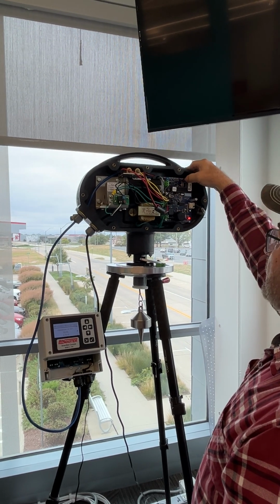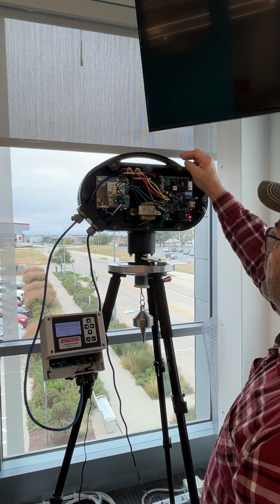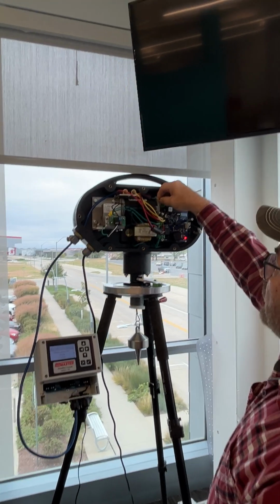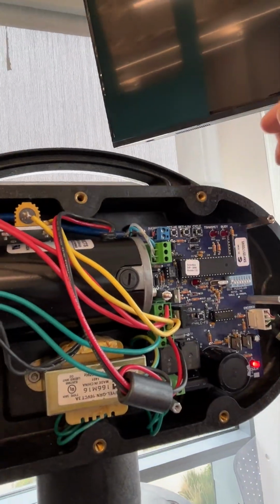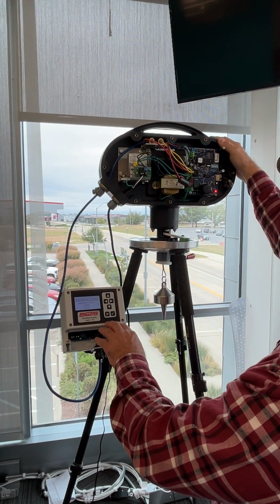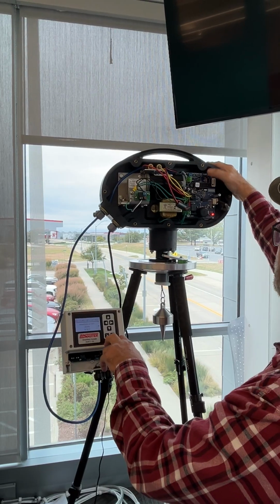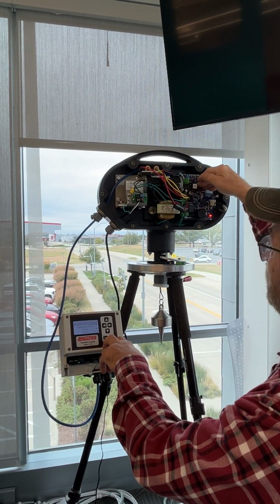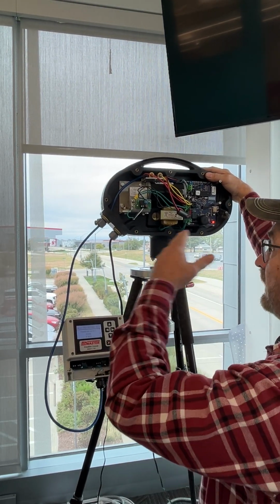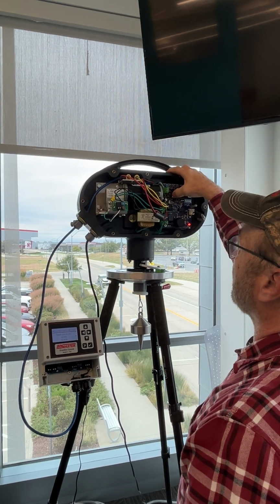If you don't see anything happen up here, check and make sure that this plug is plugged in good, this top one, it's your RS485 plug, that all the wires are secure in the terminal good right there, that you can't pull them out. If you still don't see a measurement request or either of these lights flash, you're still not getting in here. Now, it could be a problem with your board. If you have other SmartBobs that you're daisy chained into, if they all work and you just got the one, it's more likely a problem on the board.